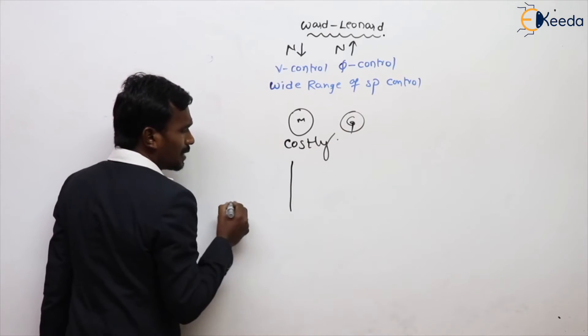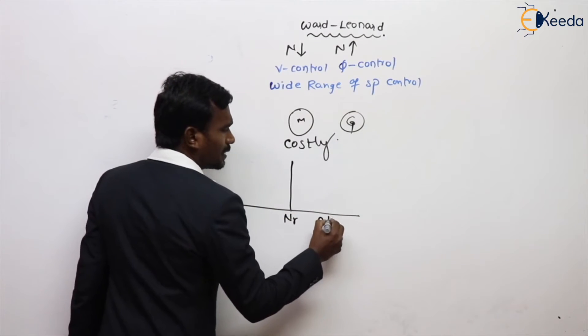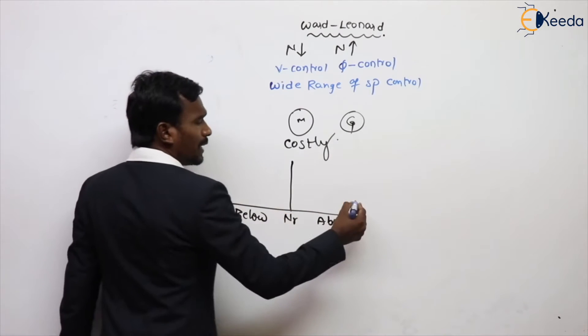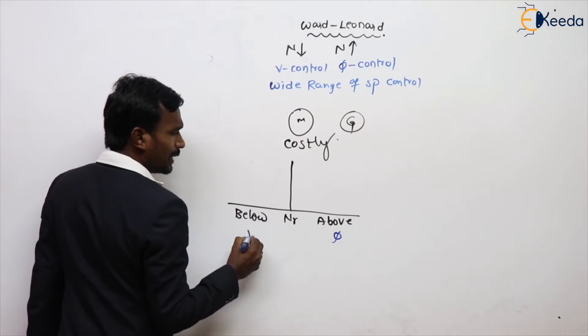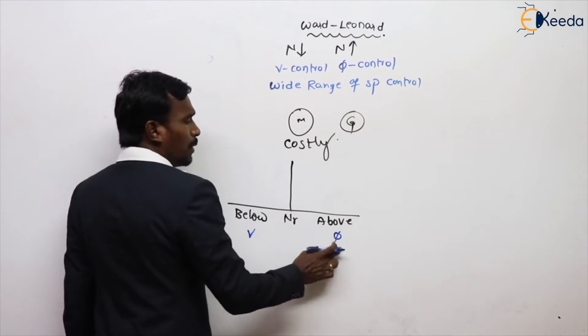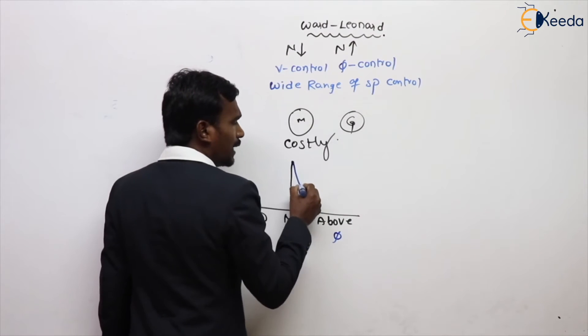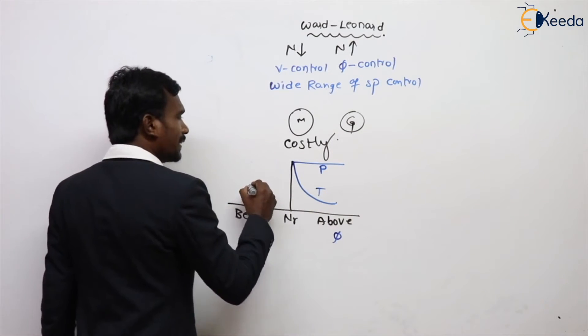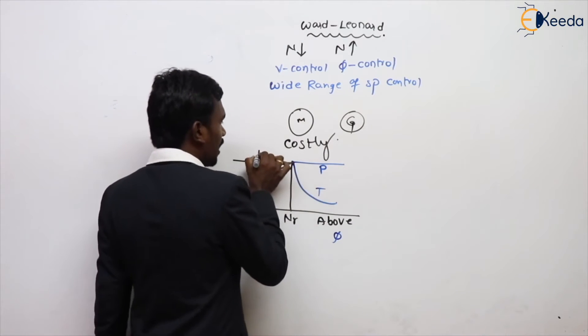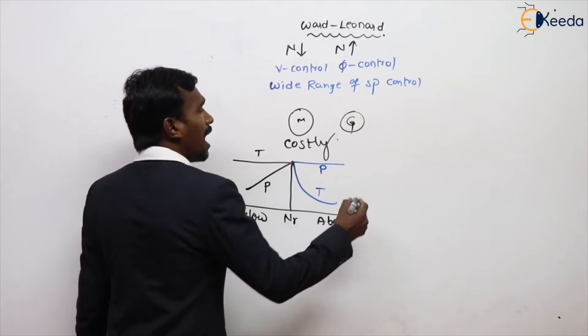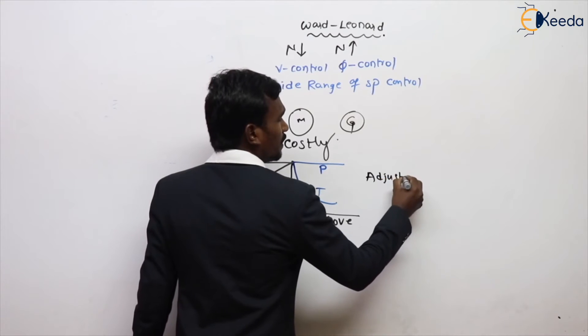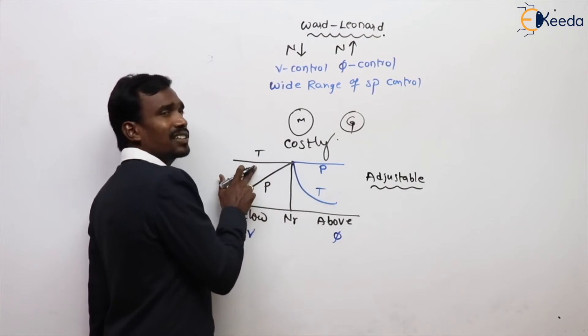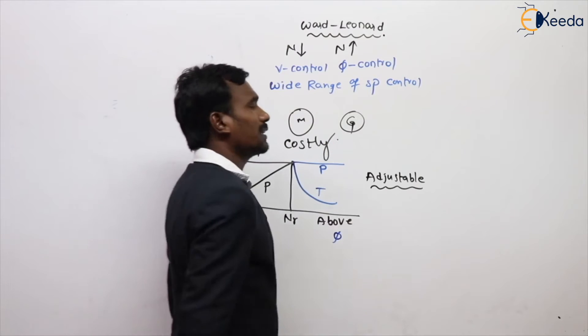Generally, we can see from the graph: this is the rated speed, this is the above rated speed, and this is the below rated speed. For above rated speed, flux control method is used; for below rated speed, voltage control method is used. In above rated speed, torque is variable and power is constant — constant power variable torque drive. For below rated speed, power is variable and torque is constant. So Ward-Leonard control is an adjustable drive — constant power variable torque and variable power constant torque — both below rated and above rated speeds are possible.